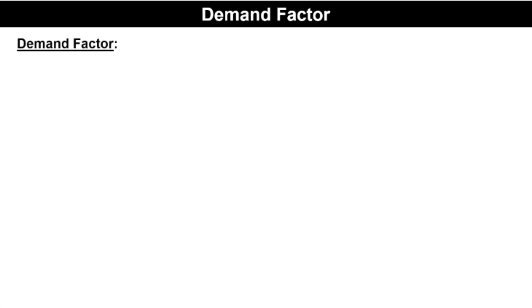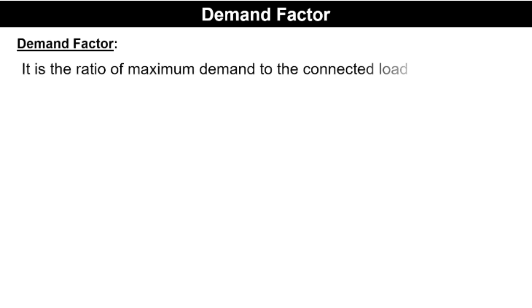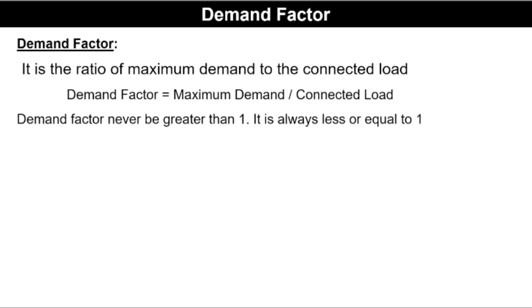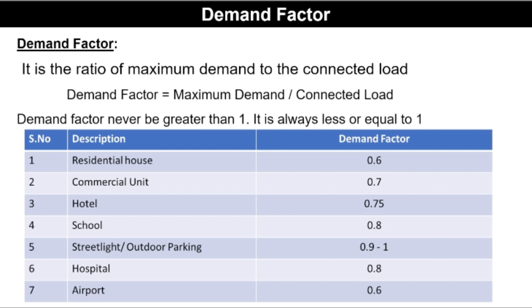Now we will see the demand factor. The demand factor is the ratio of maximum demand to the connected load. The demand factor is always less than or equal to 1, because the maximum demand is never greater than the connected load. The demand factor of various buildings: residential building — 0.6, commercial unit — 0.7, hotels — 0.75, schools — 0.8, street lighting and outdoor parking — 0.9 to 1.0, hospital — 0.8, and airport — 0.6.